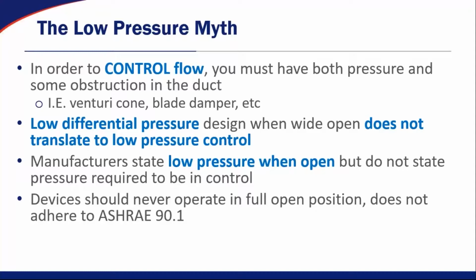So many manufacturers state their low pressure when it's open, but they don't state the pressure required to be in control. One other thing to think about: ASHRAE 130 devices, when they put those flow numbers inside of their chart in their sales literature, they're talking about being full open position.